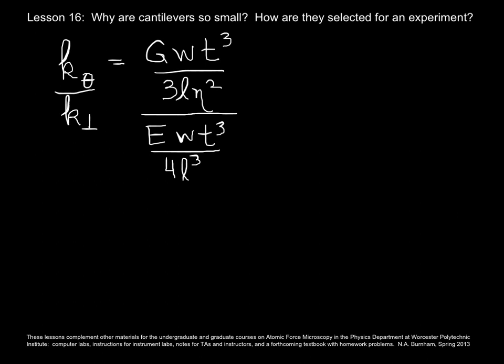Let's say you wanted a cantilever for an experiment that was very stiff in the lateral, or the torsional direction, resistant to friction, but very compliant in the normal direction, so very low spring constant. What you can do to figure out which one to purchase, or perhaps you're a designer of cantilevers, is to divide one spring constant by the other, and then look at what that tells you. So here are those two expressions for the torsional and normal spring constant. We see a lot of cancellations for the width, for the thickness, and one factor of L.